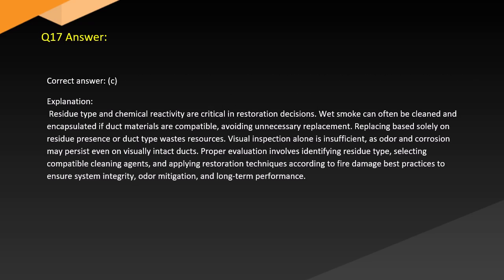Answer. Correct answer. C. Explanation. Residue type and chemical reactivity are critical in restoration decisions. Wet smoke can often be cleaned and encapsulated if duct materials are compatible, avoiding unnecessary replacement. Replacing based solely on residue presence or duct type wastes resources. Visual inspection alone is insufficient as odor and corrosion may persist even on visually intact ducts. Proper evaluation involves identifying residue type, selecting compatible cleaning agents, and applying restoration techniques according to fire damage best practices to ensure system integrity, odor mitigation, and long-term performance.